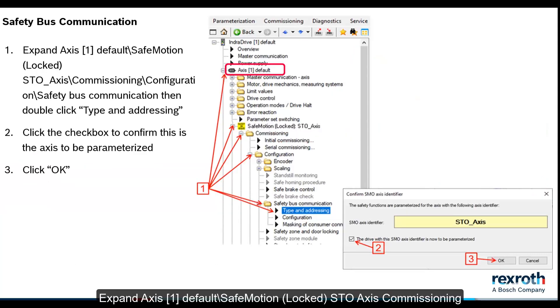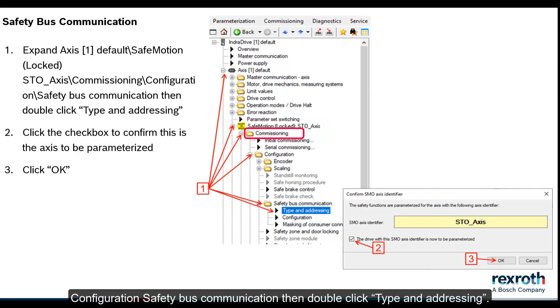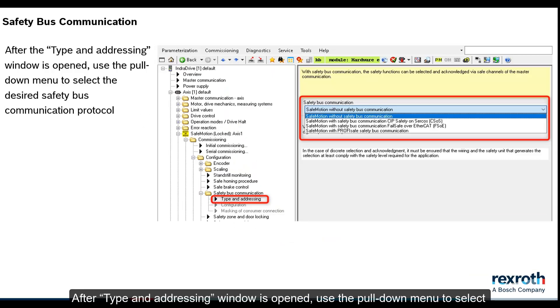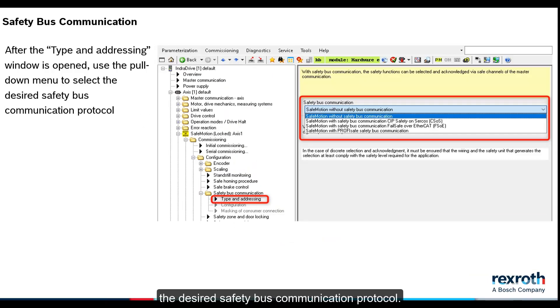Expand axis 1 default safe motion, locked, STO axis, commissioning, configuration, safety bus communication. Then double-click type and addressing. Click the checkbox to confirm this is the axis to be parameterized. Click OK. After the type and addressing window is opened, use the pull-down menu to select the desired safety bus communication protocol.